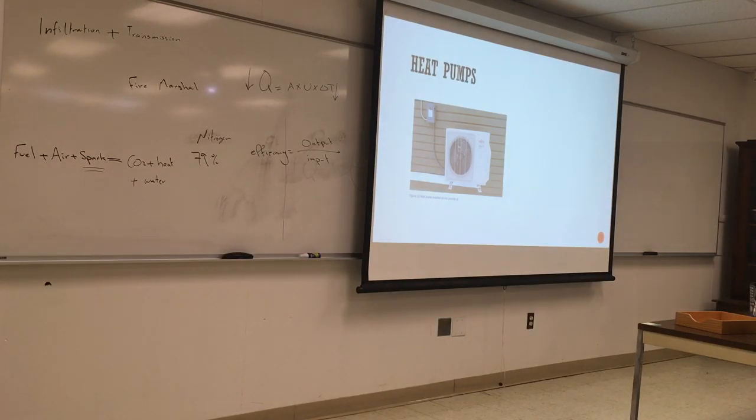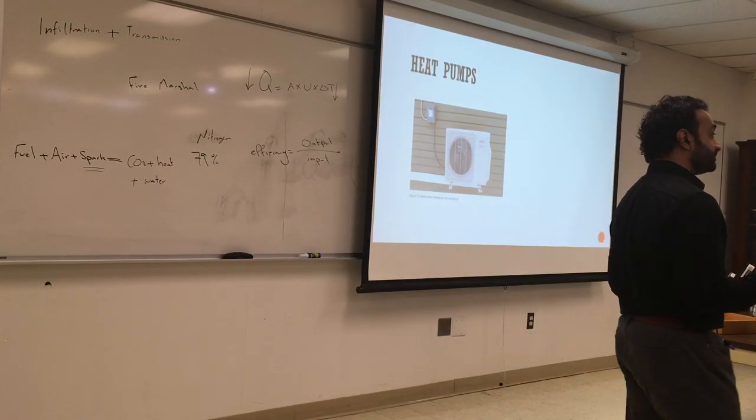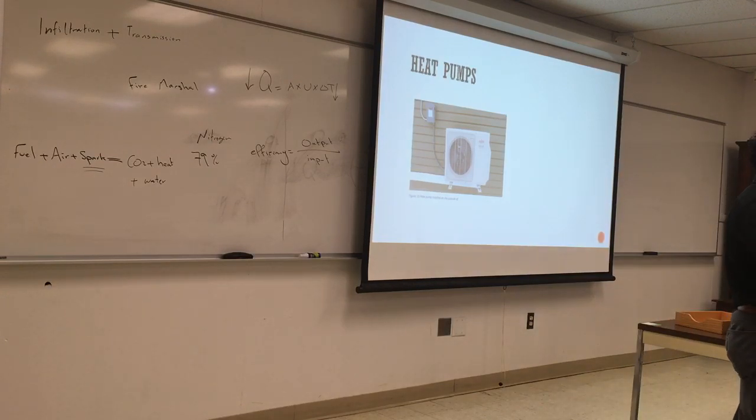However, it's not an option that you can rely on completely. So as we said, as the temperature difference increases, the efficiency will decrease. It will consume more power. The compressor has to pump harder. So if you have heat pumps, it would be a great decision to heat the house from at least March till December. From January and February, probably you're going to have some kind of backup heat. Otherwise, some big systems will have a heating coil in them, subsidized for the extra heat. And that will run your heating bill very high.